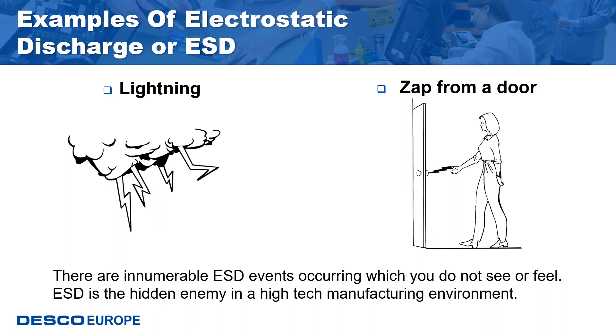It takes a discharge greater than 2,000 volts for a person to feel it. ESD is the hidden enemy in a high-tech manufacturing environment — just because you cannot see or feel an ESD event does not mean ESD events are not occurring. Human beings are insensitive unless the ESD is somewhat above 2,000 volts, yet many electronic components can be damaged by much smaller discharges. ESD control is necessary to prevent innumerable little lightning bolts — ESD events — from occurring.